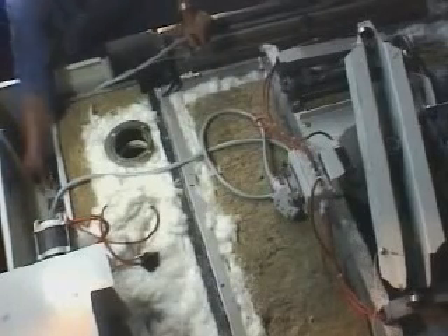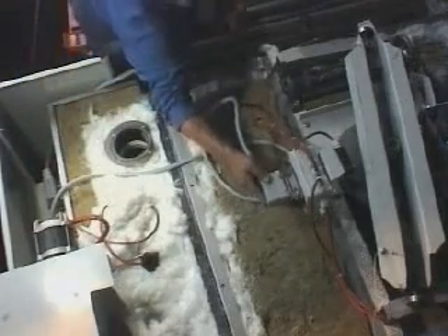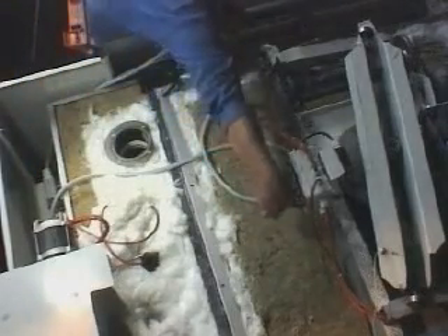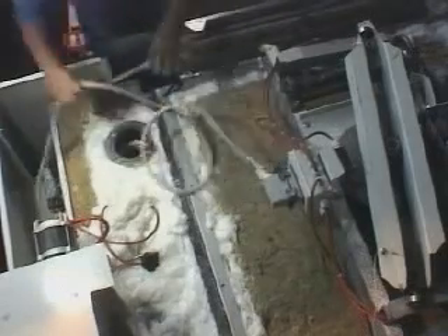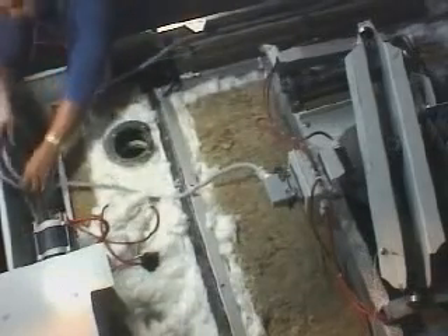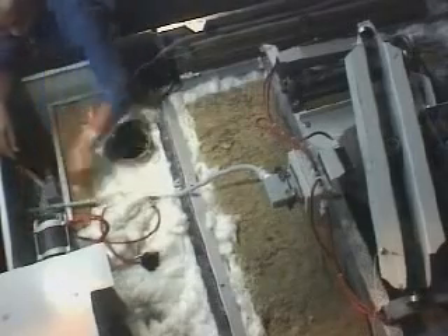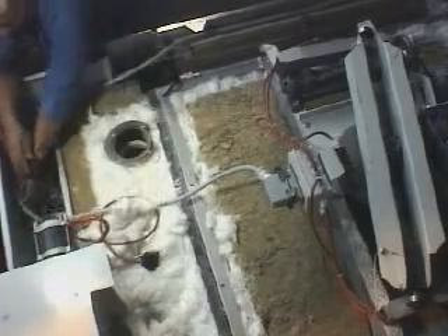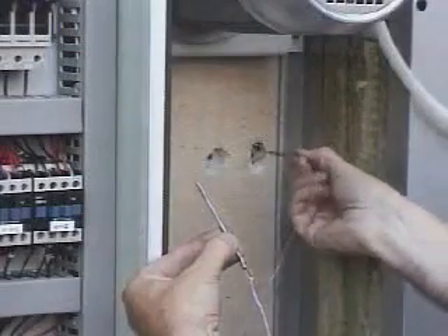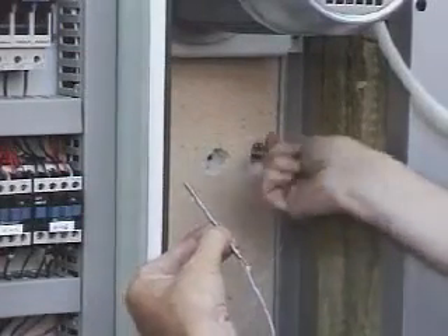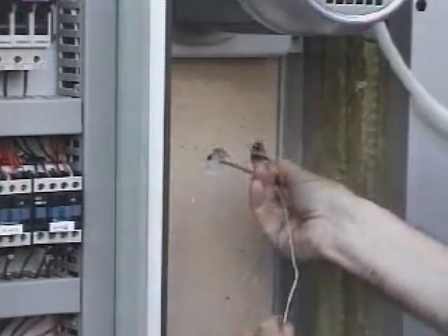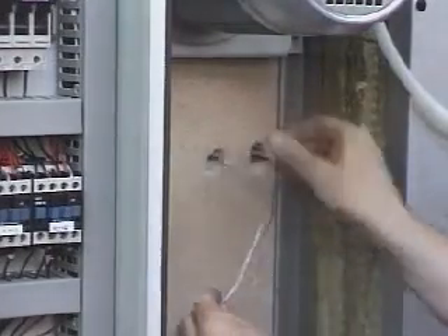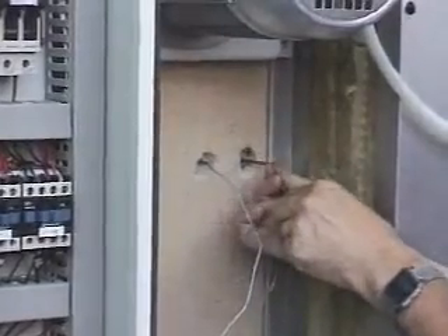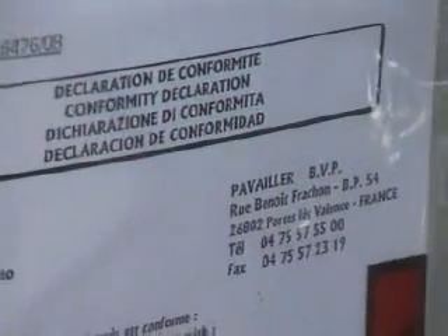Take care. Distance the cables from the heating points by placing them in the cable paths on the top strips or in cold zones. Position the temperature safety sensor and insert the safety thermostat bulb to the same depth. Insert the fume safety probe in the gas outlet port.